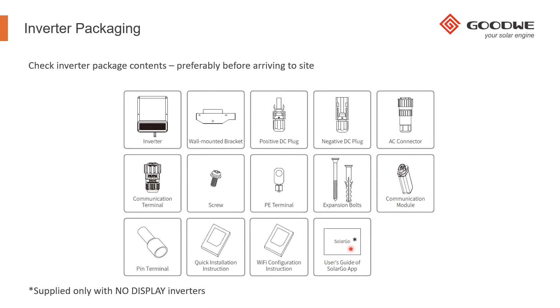We also recommend that you avoid installing the inverter in locations which have direct exposure to sunlight, rain and snow. The inverters are equipped with an IP65 rating, so they can be installed outdoors, but it's always preferable to install them underneath, for example, the eave of a roof. If you have to install them outside, in the Northern Hemisphere where we are now, a good place to install an inverter would be on the north facing side of a wall, which doesn't receive a lot of direct sun throughout the day.